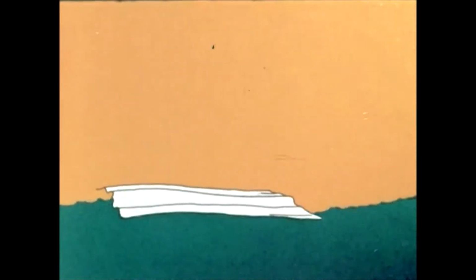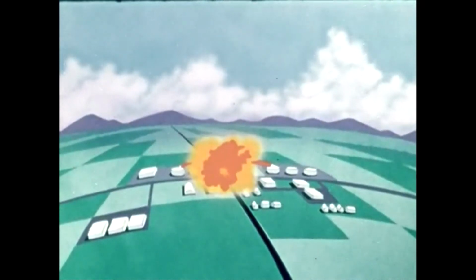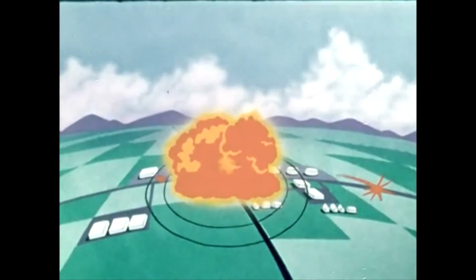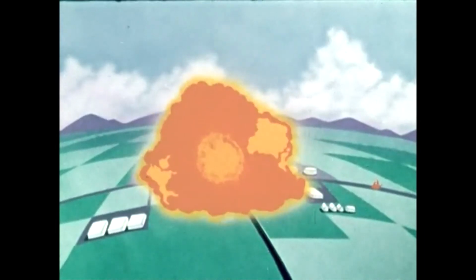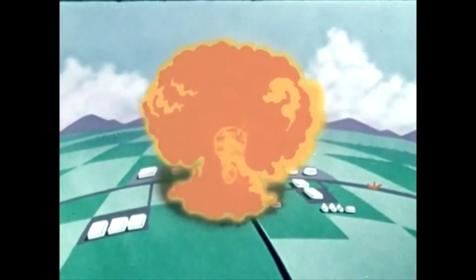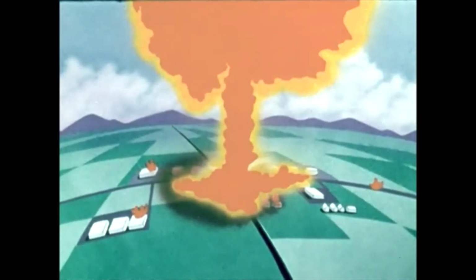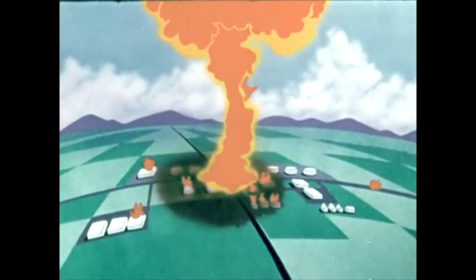Large sections of the tank car can rocket over 1/2 mile and often trail ignited liquid. The ground flash covers an area hundreds of feet in diameter. The blast wave has tremendous force, enough to break windows several miles away. The fireball rises on a thermal column, radiating heat severe enough to cause burns for distances up to 1,000 feet beyond the fireball. This all happens swiftly and without warning.